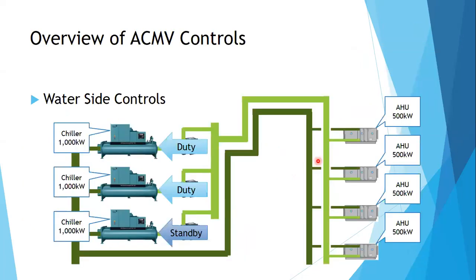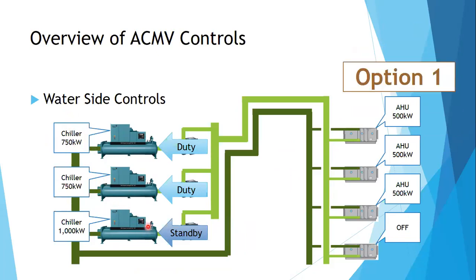Right. So example, for equipments, for air handling units, for duty air handling units. The counterpart is 3 chillers, 2 duty, 1 standby. Okay. Option 1. So this air handling unit is turned off. What's going to happen? So either you can see either this 2 chillers lower down, same, equal. So this is 1,500 kilowatt. This is also 1,500 kilowatt.